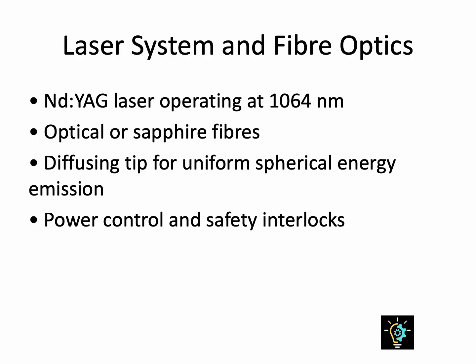The laser source, often Nd:YAG, produces near-infrared light that penetrates brain tissue efficiently. Energy is delivered through flexible optical fibers designed to withstand high thermal loads. Sapphire fibers are preferred for their durability and low absorption losses. At the distal end, a diffusing tip scatters light evenly, creating a symmetrical thermal field. Engineers implement interlock systems and temperature-limited feedback to prevent overexposure. Cooling channels circulate saline around the fiber to dissipate excess heat. The precision of this delivery system determines both treatment effectiveness and tissue protection.